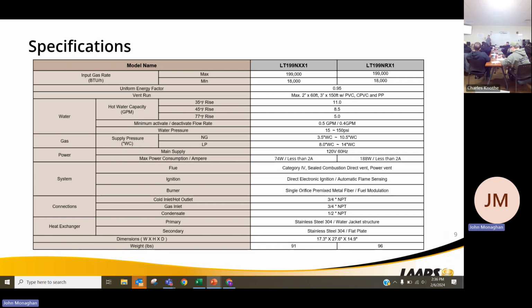Your spec sheet with it, again, it's only one size. It's 199,000 BTUs. Lowest firing rate is going to be 18,000 BTUs, so it is going to modulate. Trying to make it easy for the wholesalers and for the contractors. There's not multiple different SKUs. Most of the time, if we're doing anything with a combi or a tankless water heater, we're looking to shoot for that 199,000 BTUs because that seems to get us our magic 5 gallons a minute, as what everyone seems to want.